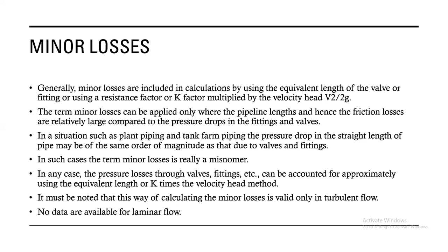It must be noted that this way of calculating the minor losses is valid only in turbulent flow. Note that flows in industry are always, or usually, only in the turbulent flow regime.